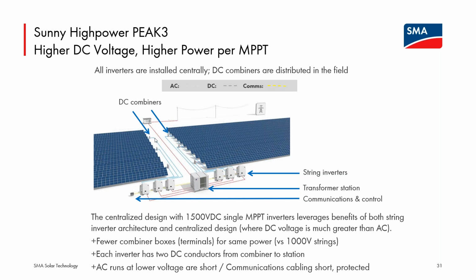Obviously, there will be combiner boxes. Those can be out at the array, but then you have the longer runs from the array to the inverters be the DC side, the higher voltage side. Even for the 600 volt units, the DC side should be higher voltage than the AC side. Run the power for longer distance on the higher voltage, thus lower current, lower loss line, and have the AC runs be as short as possible.